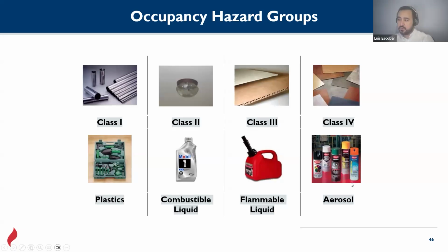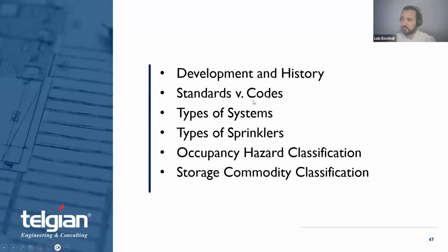Plastics, combustible liquids, flammable liquids, and aerosols can also be explosive, so they're pretty dangerous. Okay, so now we know a little bit more about all these topics, about commodity classifications and what type of sprinkler we might need. For example, if we're building a hospital, we're going to need a wet system. It doesn't make sense to have a pre-action system for a break room. That's basically the intention of this training or course, to provide a little more guidance when choosing a fire sprinkler system.